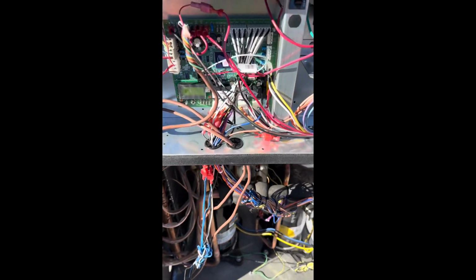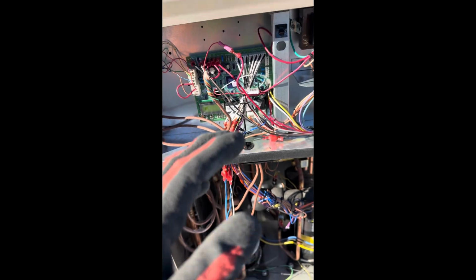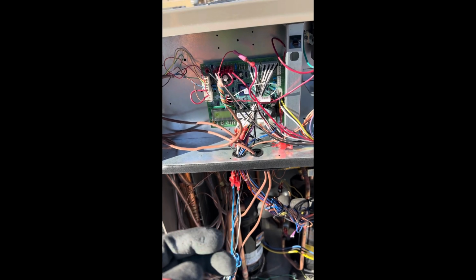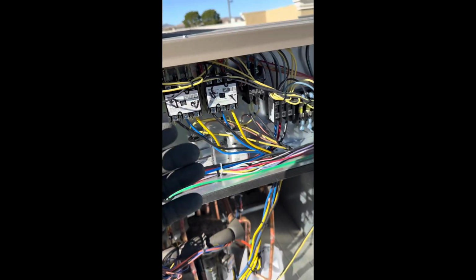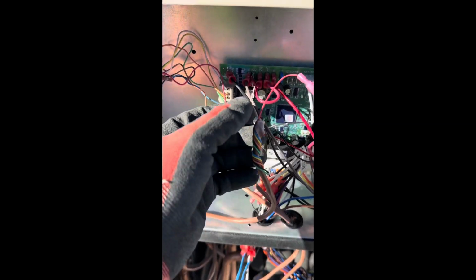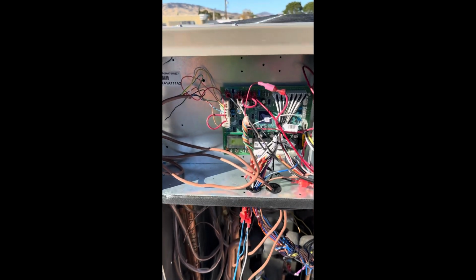Okay, a quick note here, guys, about the smoke detector wiring. There are different ways to wire this bad boy up. However, a lot of smoke detectors, you can only have one power source. Here on this project, we have the power being supplied by a separate circuit of 120 volts. Normally, if you want to power the smoke detector, you can use these 2 terminals here, SD24, SDR. This is the in and out of hot for 24 to supply power to the duct detector. However, since we are powered, we really would just want to break the circuit to the circuit board so we can turn off the compressor, fans, and indoor fan in case of a shutdown or an emergency. So here what basically we are doing is just we're gonna break the 24 volt hot leg to the UCB. As you can see, it's powered off right now because I'm testing smoke detectors. And that was just my quick tidbit on that.